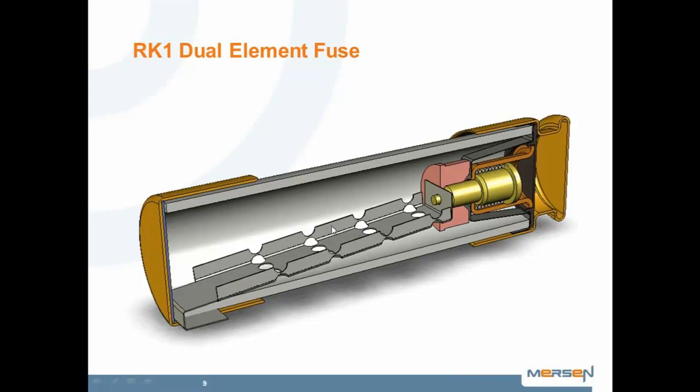And the way it works is that if you have a short circuit, it will melt the weak links here and melt the silica sand in it, and the silica sand will turn to glass, molten glass, sometimes called fulgurites, and it will have a high resistance. The amazing thing about this is not time dependent.